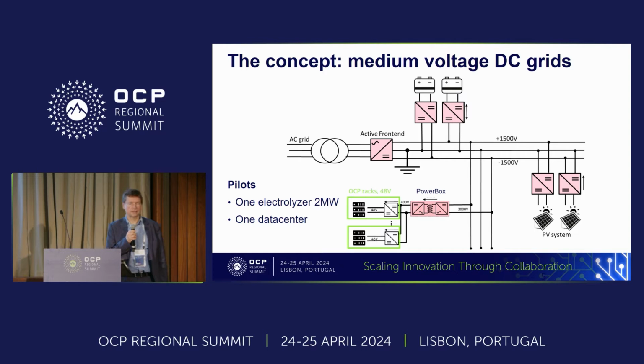Why this value of 1500 volts? Because actually a low voltage grid is 1500 volts and a lot of protection devices are available for this voltage level. So what we are doing actually here in order to increase voltage is to combine in series two low voltage DC grids. So we have one DC grid at 1500, another one at minus 1500, we combine this and then we can power the servers with 3 kilovolts. The advantage of this is that you gain a lot of flexibility, modularity, and reduced planning efforts. So you also gain in efficiency.